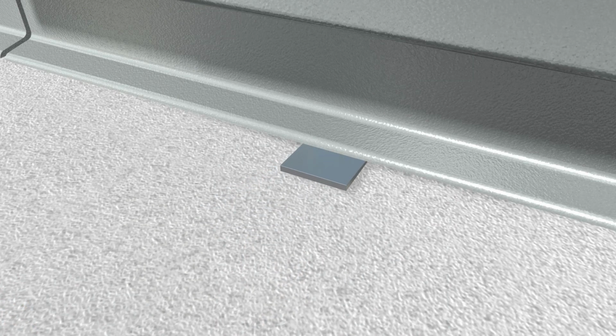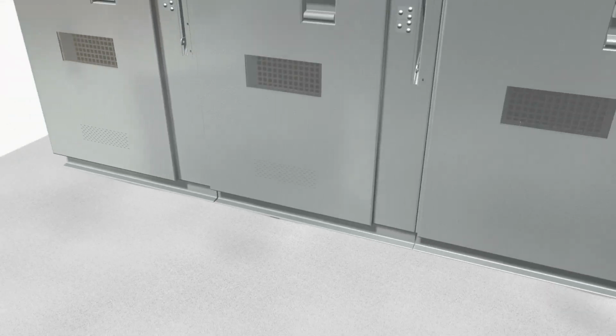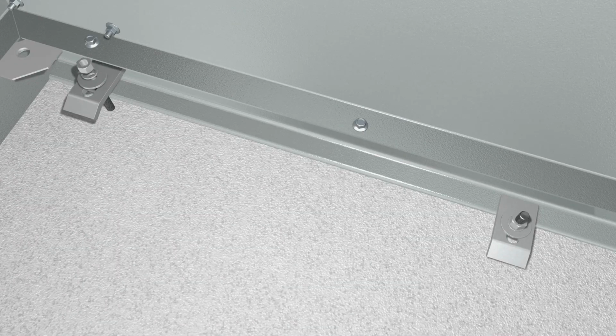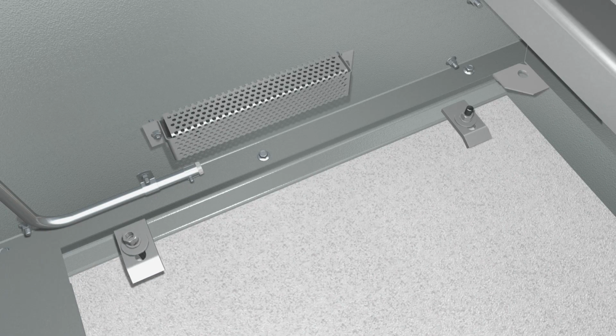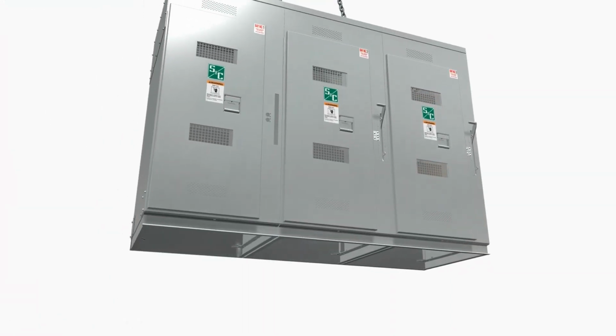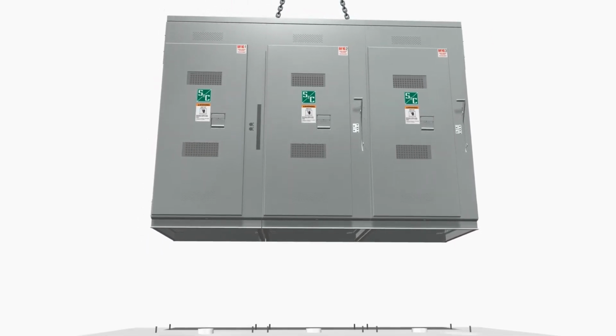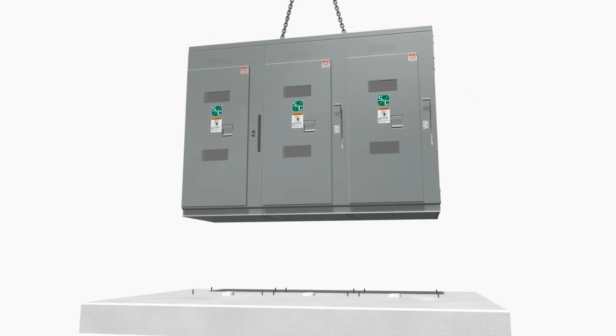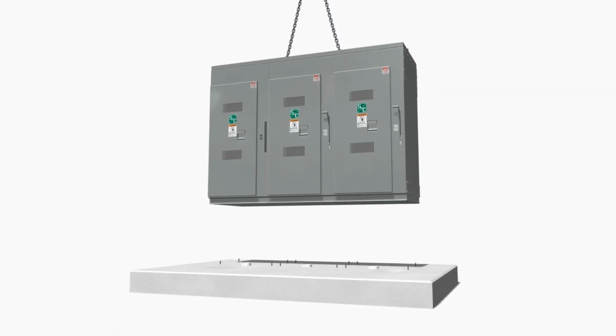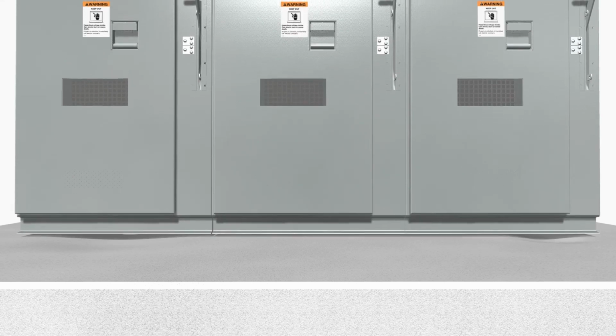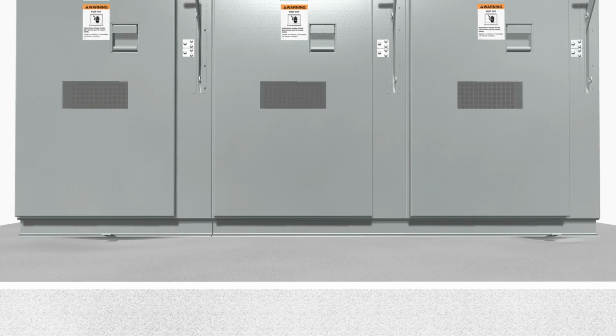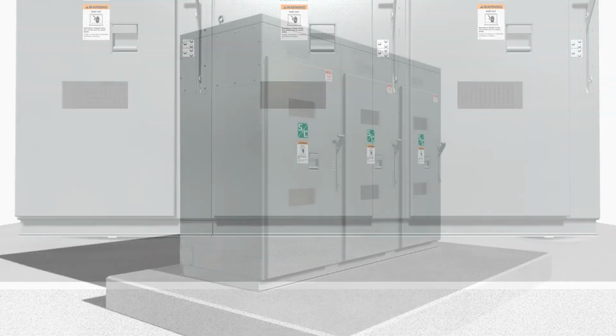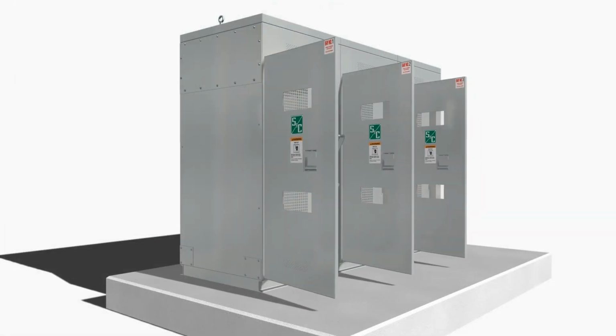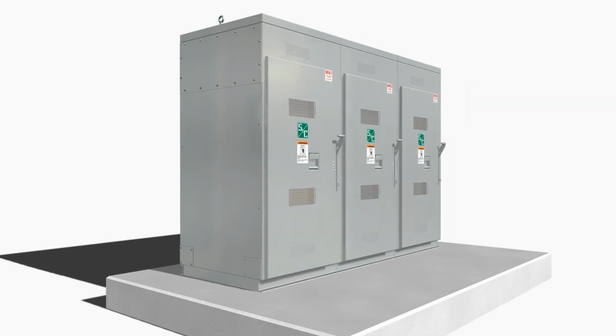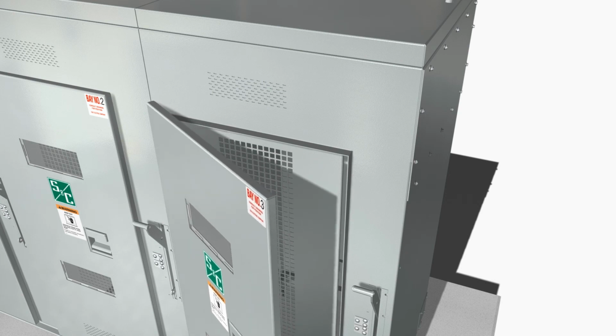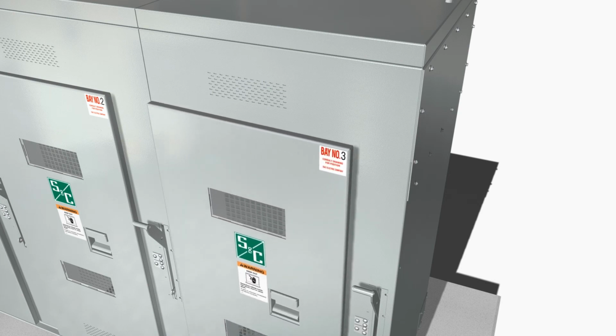Step 5. Level the bay using metal shims as required. Secure each bay to the pad with the anchor clips provided by tightening the anchor bolt nuts. On multi-bay assemblies, avoid misalignment, which may result in improper operation of the switchgear and ineffective weather sealing between bays. Before installing the switchgear, determine where shimming will be necessary and have the required shims on hand. Make sure the switchgear bay doors open and close without binding. Binding indicates enclosure distortion, which must be corrected by additional shimming.